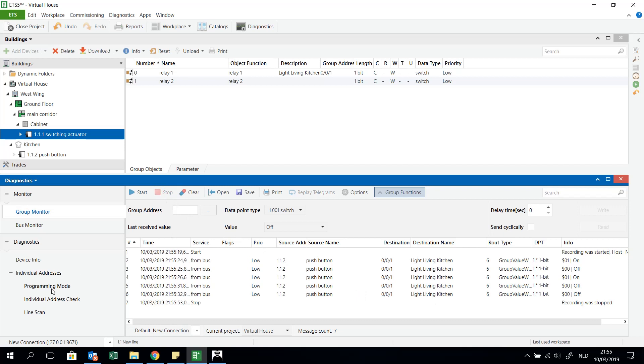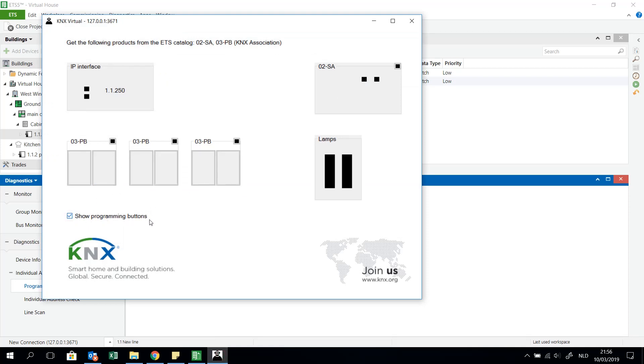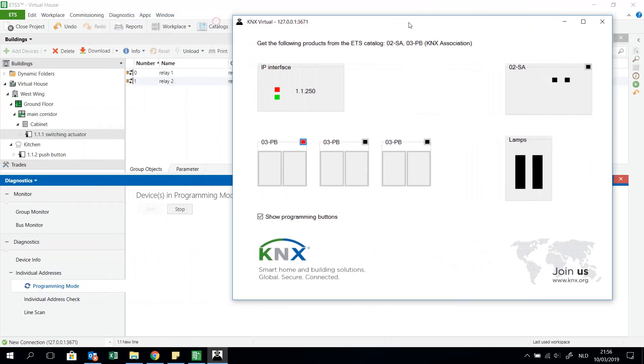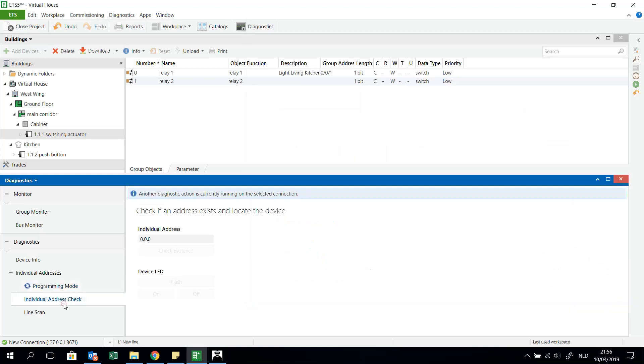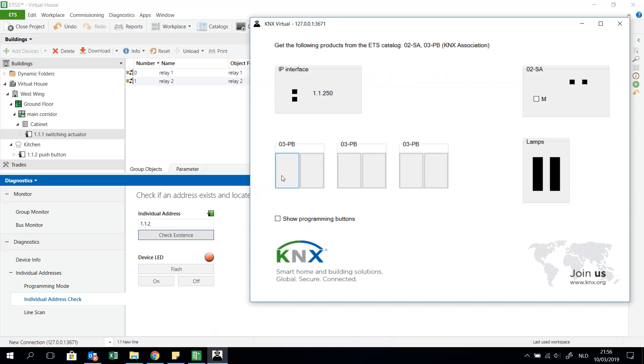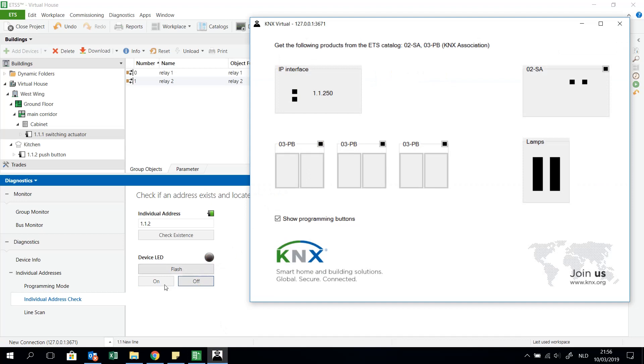I can also do other things, for example checking which devices are in programming mode. I show the programming buttons and put one device into programming mode. When I start the scan, it immediately identifies it as the push button interface with individual address 1.1.2 — very interesting. I stop programming mode, then do an individual address check: does this component exist on the bus? Yes, it exists. I can also flash the LED — I show the programming buttons and see the light flashing. I can stop flashing, turn on the device LED, or turn it off.